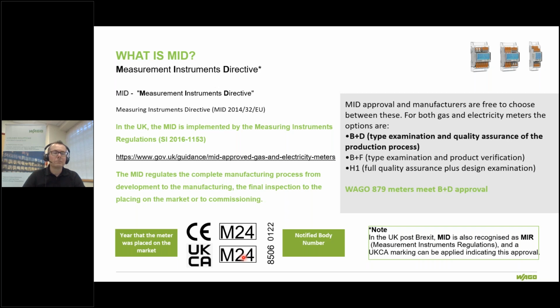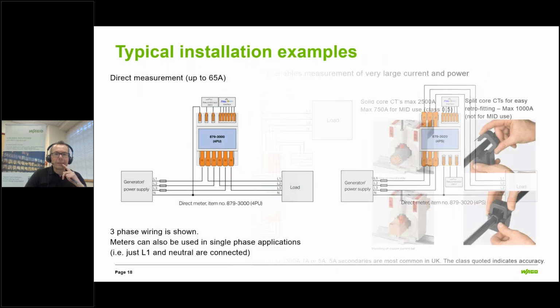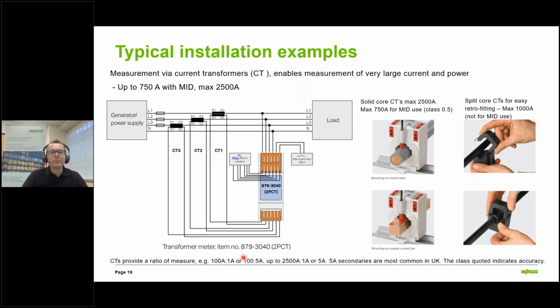Next one is the CT options for the 879. Is it up to 2500 amp on each phase? Yes, so if I remember which way to go on the slides, I can show you that again. Yes, here we are. So if it was just being used on a single phase, you'd have a single CT on L1 and neutral is just directly connected from the load to the supply with a tap off to the meter for voltage reference. So yes, a single CT on a single phase.